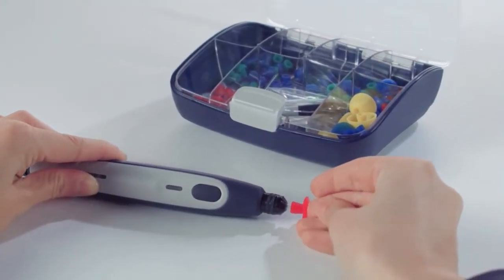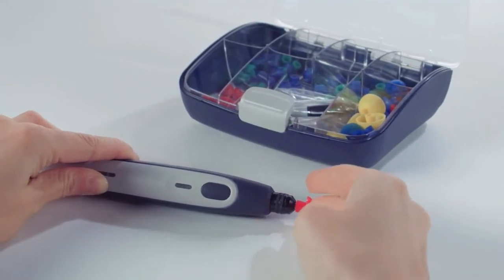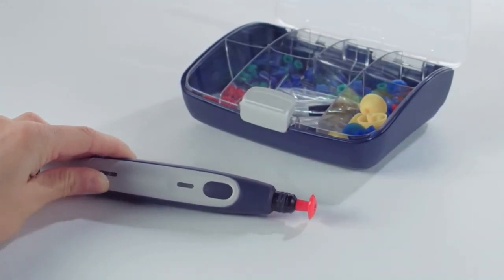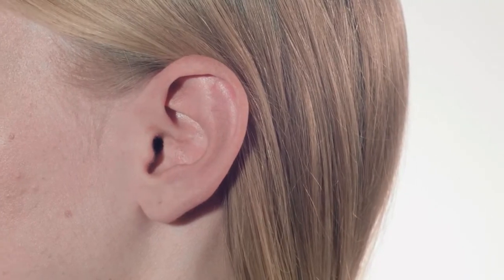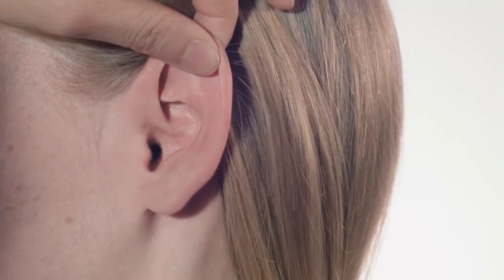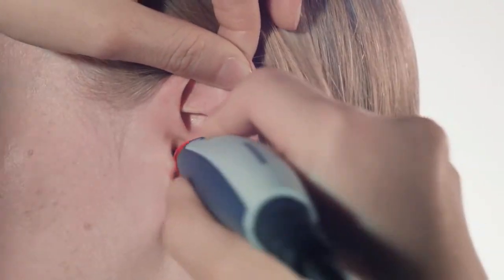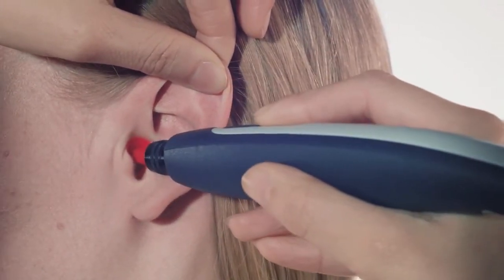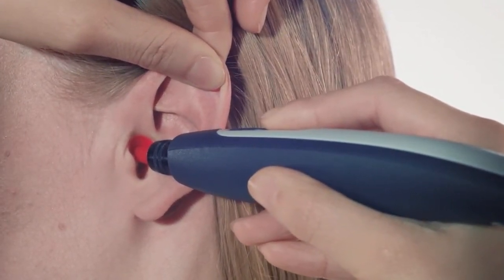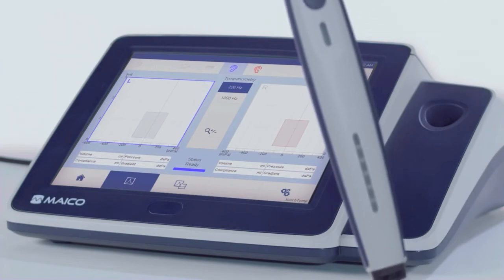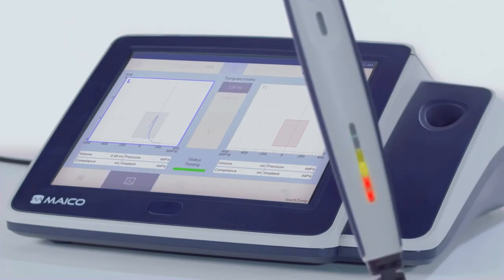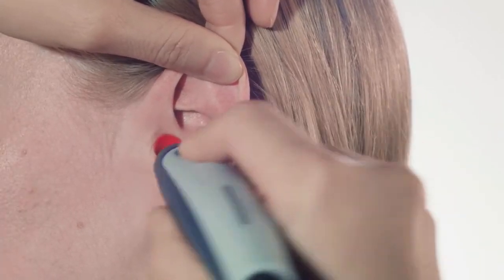When placing an ear tip on the probe, make sure the ear tip is pushed all the way down on the probe tip. Gently pull the ear up and back for adults, or down and back for infants, to straighten the ear canal. Hold the probe in place, applying slight pressure so a seal can be obtained throughout the test. The light bar at the bottom of the probe provides a real-time progression of the test. This function allows you to focus completely on the patient.